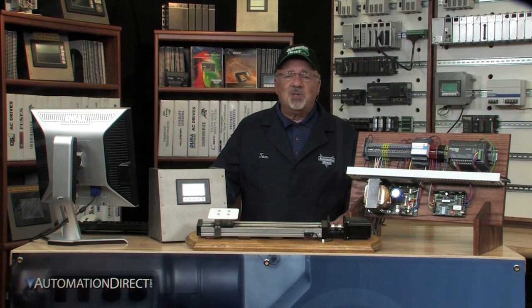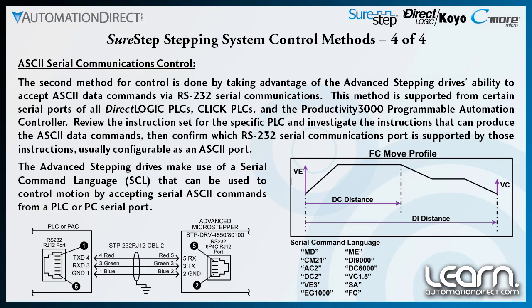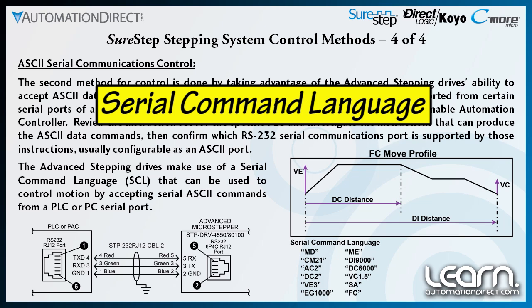The second method for control is accomplished by taking advantage of the Advanced Stepping Drive's ability to accept ASCII data commands using RS232 Serial Communications. The ASCII Serial Communications method is supported from certain serial ports using any DirectLogic PLC, CLICK PLC, or the Productivity 3000 programmable automation controller. Check the instruction set for the specific PLC being used and confirm which RS232 Serial Communications port is supported. The Advanced Stepping Drives make use of a Serial Command Language, abbreviated SCL, which is used to program motion profiles accepted as Serial ASCII commands from a PLC or PC serial port.